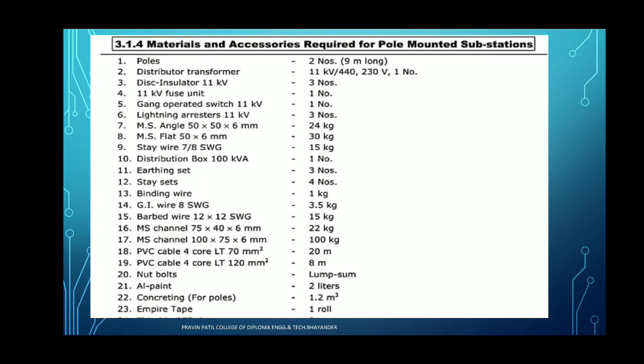Then disc insulators of 11 kV rating, 3 disc insulators are required for the pole mounted substation. Then an 11 kV fuse unit, 1 fuse is required as an accessory for the pole mounted substation. Then a gang operated switch of 11 kV rating, that is also required, one quantity. Lightning arrestors of 11 kV, 3 quantities are required for the pole mounted substation.